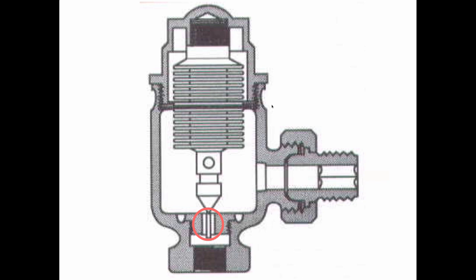At this point you need at least a ten degree drop in temperature from one side of this trap to the other before it'll open. If it's not doing that, the trap's not working.